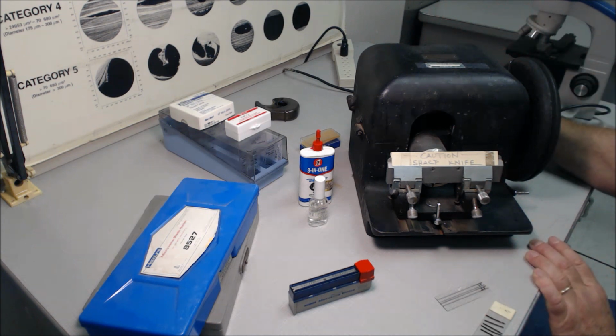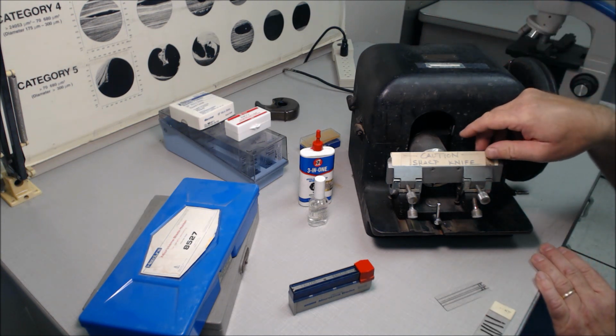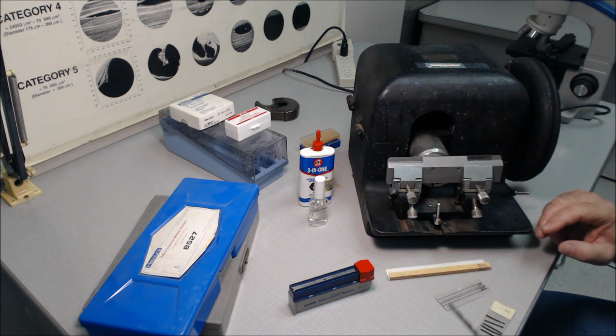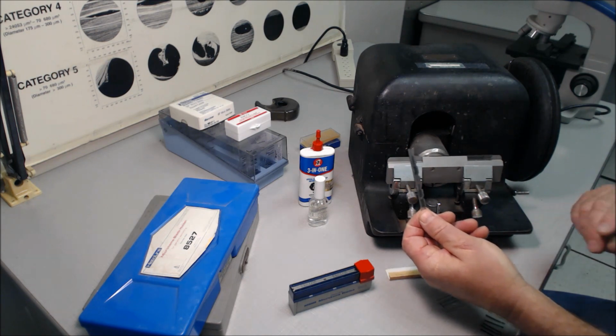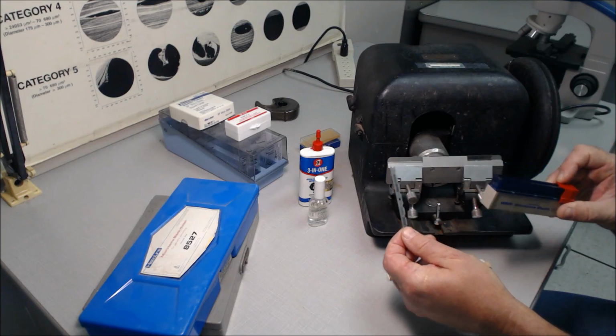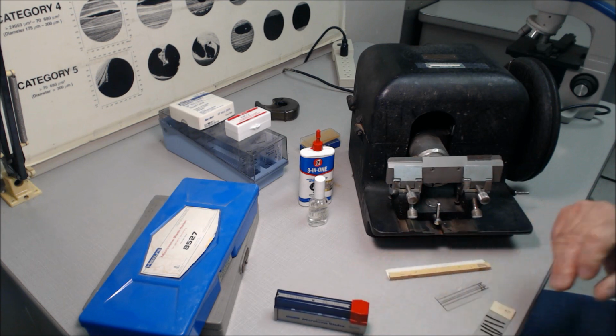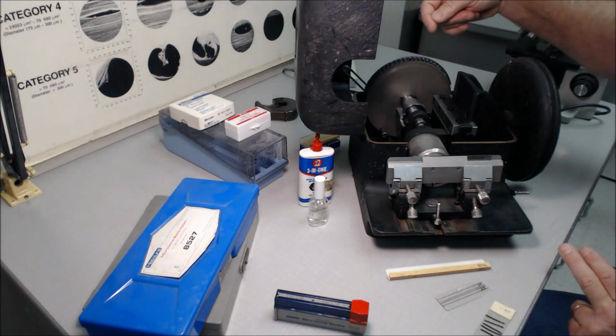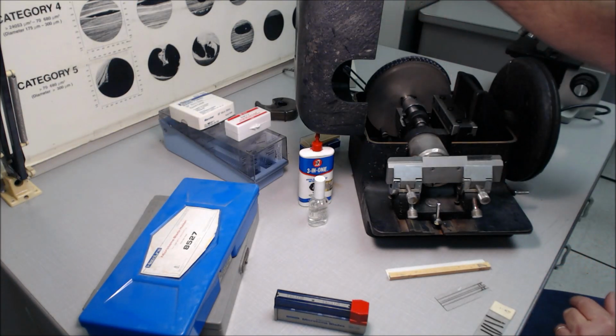This is a very old one, but still very rigid and works very well. Please be cautious, there's an extremely sharp knife here. This knife has replacement blades associated with it, and these blades are extremely sharp and quite dangerous if handled improperly. This apparatus incrementally moves the specimen up, and then the knife will cut it.